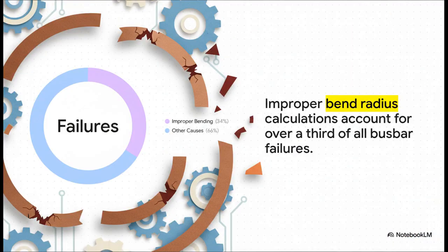Bending a thick piece of metal might sound simple, but it is incredibly complex. Getting that bend radius wrong, just a little bit off, is a factor in over 1/3 of all busbar failures. It creates invisible stress points that can lead to catastrophic cracks over time.